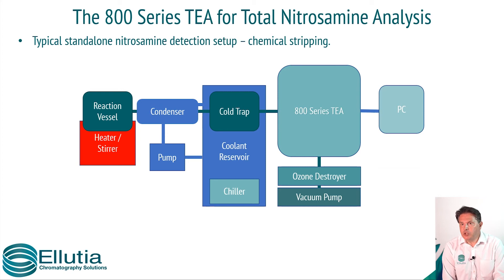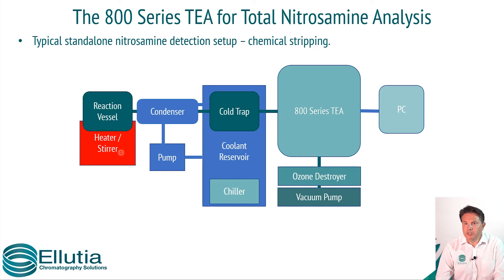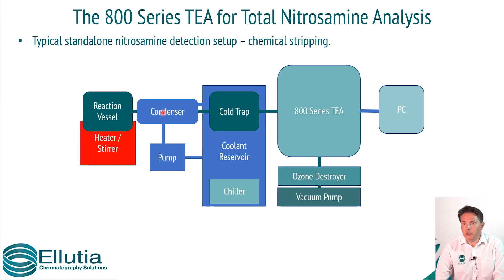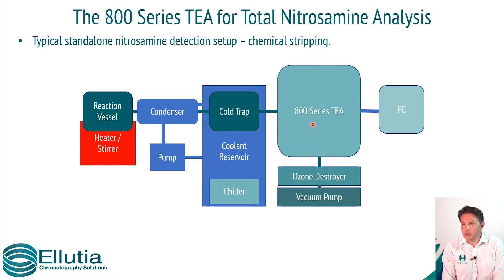This is a generic layout for our glassware system for total nitrosamine analysis. We have a reaction vessel that will contain our hydrogen bromide reagent. This is heated to reflux conditions to release the nitrosyl group. Gases enter the condenser, which crashes out the reaction mixture. This then passes through a cold trap to further prevent any aqueous samples entering the TEA system. The nitrosyl group then enters the TEA system for detection.